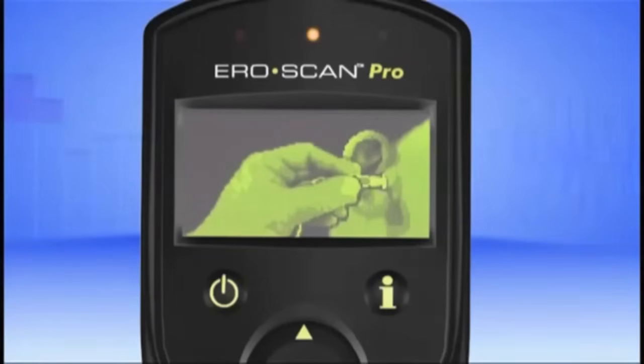This display image indicates the probe is in the ear canal, and the test will start soon as long as all other conditions of auto start process are met. If the test does not begin, this may be the result of probe instability, where the fit in the ear canal is not continually secure. Additional causes can be that the patient is too active or there is excessive noise present.